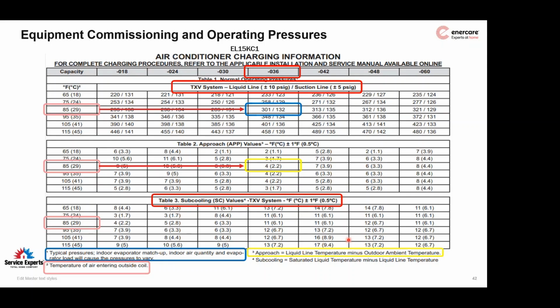And then, of course, our more likely measurement is subcooling. We're typically going to commission and validate our charges with subcooling. In this scenario, on an 85-degree day with a 3-ton unit, Lennox is going to have approximately 11 degrees of subcooling. Does anybody not know how to measure these before I move on to the next slide?